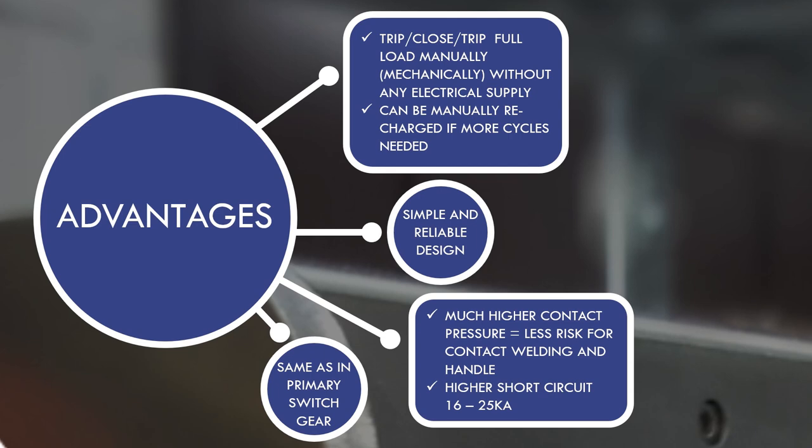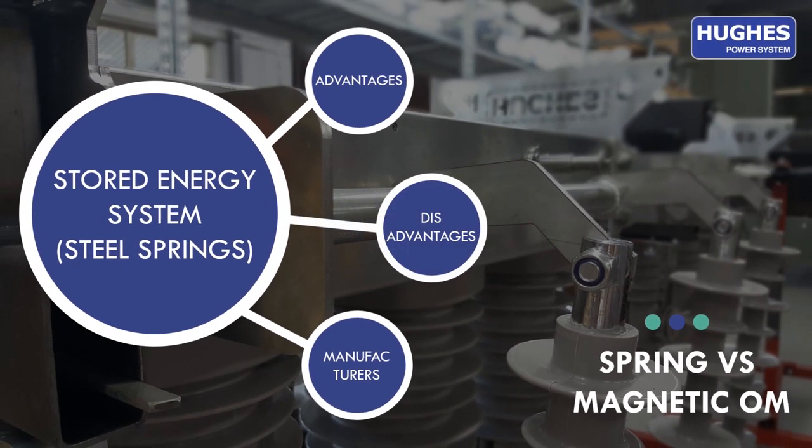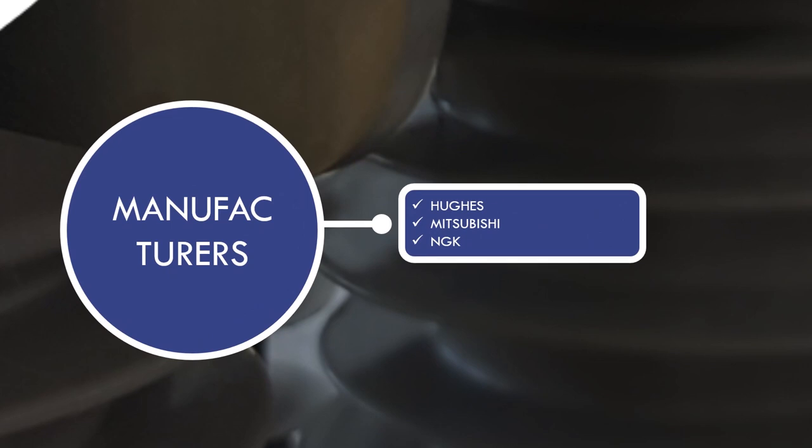If you look at the primary substation breakers, they use the same spring mechanism due to its proved reliability and much higher contact force. Moving next to the disadvantages, the stored energy mechanism is normally a little bit slower, about four shots, than a magnetic actuator as it needs to recharge automatically its springs. This type of mechanism is also more expensive than others. The manufacturers that are using spring mechanisms in their reclosers are Hughes, Mitsubishi, and NGK.